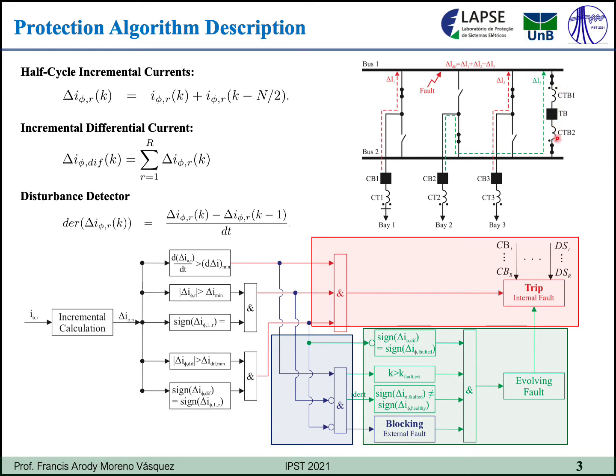Also, it must be noticed that here I have two current transformers, CTB1 and CTB2. CTB1 is connected to bus 1, and CTB2 is connected to bus 2. But CTB1 measures the current coming from bus 1 and entering into bus 2. And CTB2 is connected to bus 2, but it measures the currents entering into bus 1. So if the fault occurs at bus 1, CTB2 provides currents with the same polarity as the other contributions. So it's important to know that because it provides information about the faulted bus, as well as the feeders that must be disconnected.